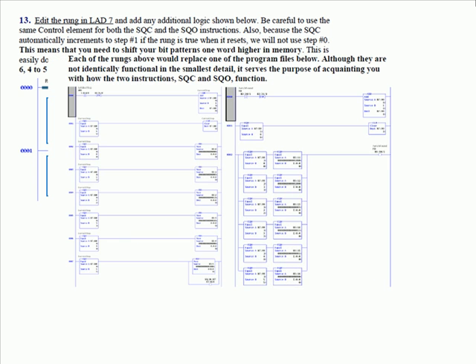When you move four to five it leaves four as a duplicate of five, then you move three into four, and so on all the way down, and then zero you would just clear. Each of those rungs above would replace one of the rung files below. Although they are not identically functional in the smallest detail, it serves the purpose of acquainting you with how the two instructions — the sequencer compare and the sequencer output — function. We have one more sequencer instruction: the sequencer load, which is a nice little instruction. If you don't have it at this point, go back to where you felt really comfortable and start over. You'll probably get more out of the ladder logic sequencing than out of the sequencer instructions. But if you're maintenance engineers, maintenance technicians, or maintenance electricians, you may inherit machines that use the SQO and the SQC instructions, so you need to understand how these instructions work.